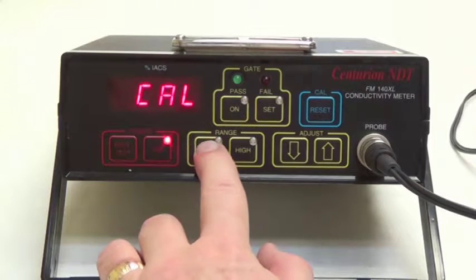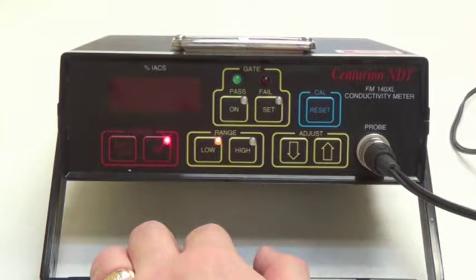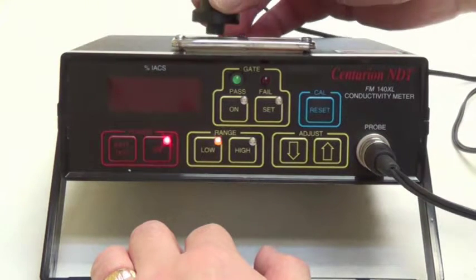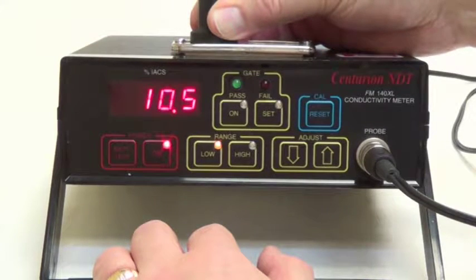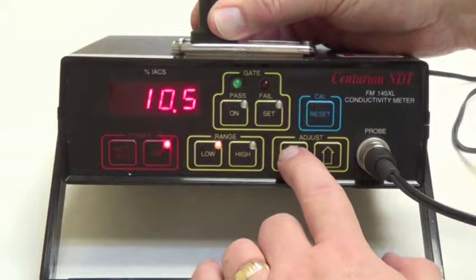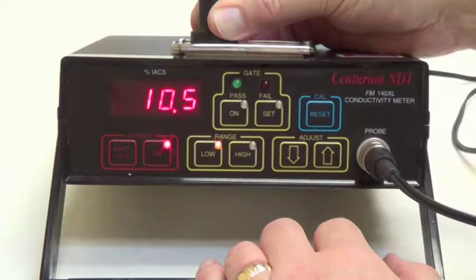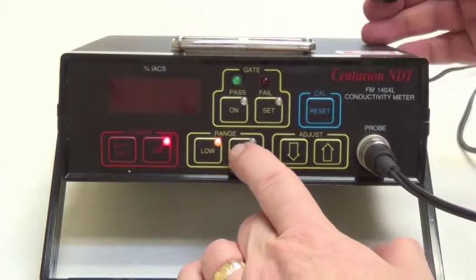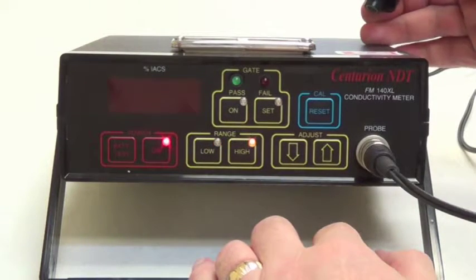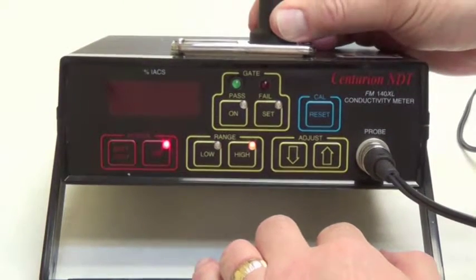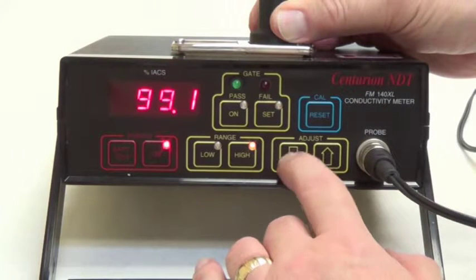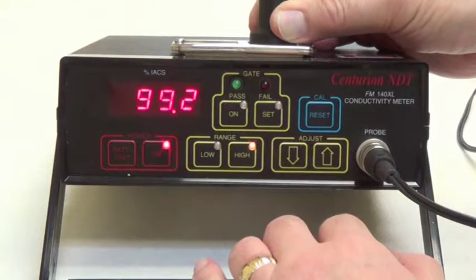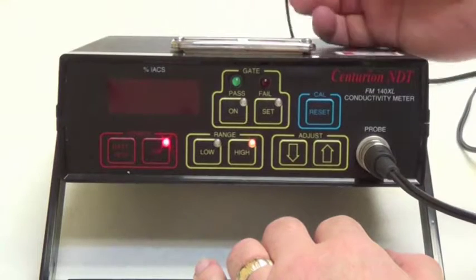Now press the low push button. The amber LED lights and the display goes blank. Place the probe on the low sample mounted on top of the instrument. Using the up and down arrow, set the display to the same value assigned to the low sample, in this case 10.5. Press the high push button and the amber LED lights. Place the probe on the high sample and using the up and down arrows again, set the display for a reading of the high sample, 99.1.